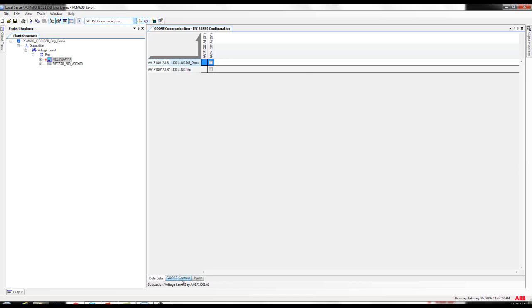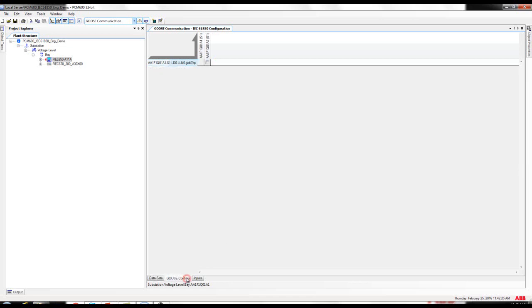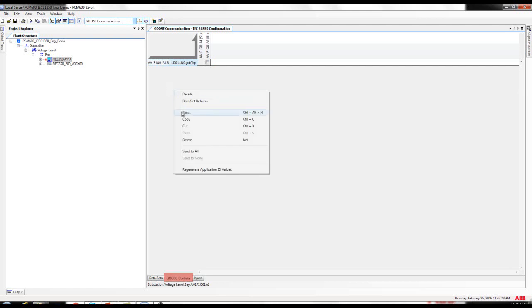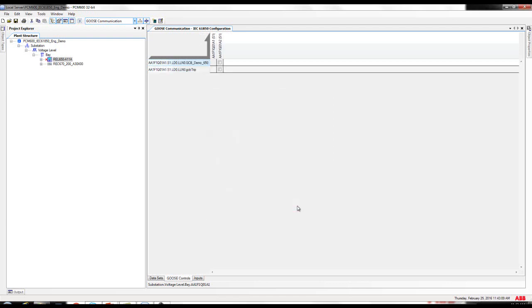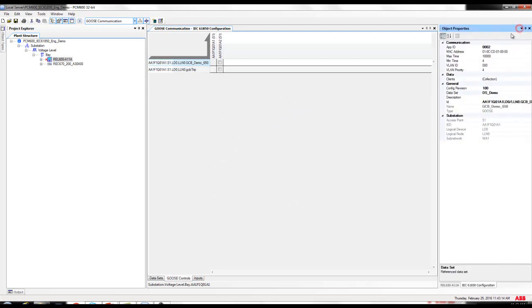The next step is to create the GOOSE control block. Click on the GOOSE control tab at the bottom, right-click, new. Choose the dataset that is going to be contained on this GOOSE control block — DSDemo in this particular case. There is no other option, only the GOOSE. Click OK, and now we have added the dataset to the GOOSE control block. If you want to make some changes to the properties of the GOOSE control block, go to the object properties on the right side of the software.